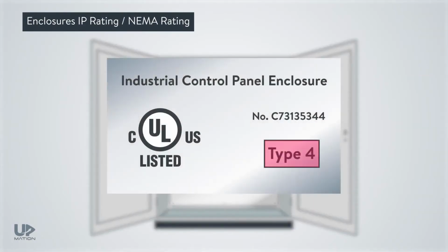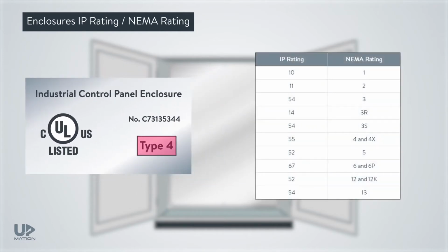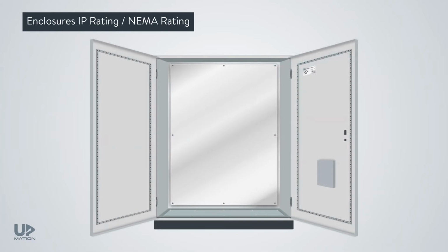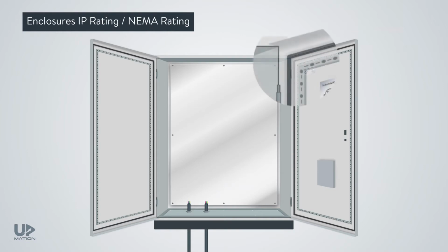NEMA ratings have the same meaning as the IP ratings, but with different styles, and most of the time you can match a specific IP rating with a NEMA rating. We'll create a comprehensive video on IP and NEMA ratings. So if our electrical panel has an IP55 rating, after we have entered the cables into the panel, it must still have this degree of protection. Thus, the glands will help us to maintain the IP rating of the electrical panels after the cabling works. Meanwhile, the ingress protection rating will be increased by some specific tapes around the doors and the gaps between the side plates of the enclosures.